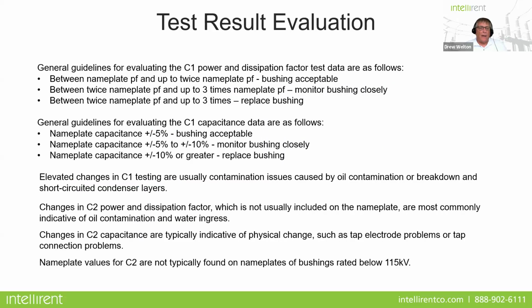If we take a close look at what these guides are telling you, you can see this right here. General guidelines for evaluating the C1 power factor test look as such. If the power factor measures up to twice the nameplate rating, that's acceptable. So if the nameplate is 0.23 and it's showing 0.4, that's okay. But between twice the nameplate and up to 3 times, you want to monitor it closely. If you don't have a bushing monitor or an online monitor, you may want to decrease the time before you test it once again. If it's over 3 times, you're definitely going to replace that bushing. In evaluating the capacitance, we're going to look at the nameplate capacitance being plus or minus 5%, which is acceptable.